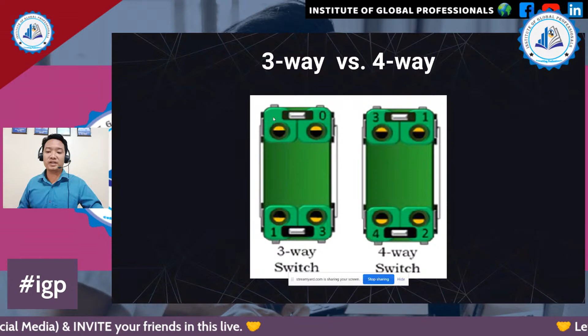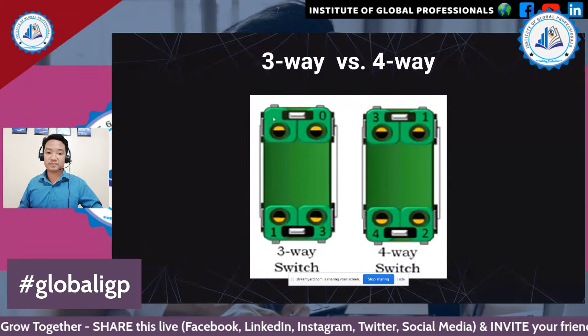In three-way versus four-way, their similarity is that they serve as travelers. They cannot serve as poles or as a single pole switch because there is no on or off in them. So they serve only as common terminals or travelers. This is now the actual connection diagram of the three-way and four-way. So let us analyze and compare the differences of the actual connection diagrams.